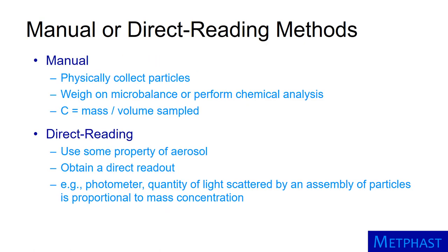The method of aerosol sampling may be manual or direct reading. In manual methods, particles are physically collected, usually onto a filter. These filters are then weighed to determine the mass of collected particles, or analyzed chemically to determine the mass of a certain composition. This weight is then divided by the air volume sampled to obtain mass concentration. In contrast, direct reading methods use some property of an aerosol to obtain a direct readout of concentration — for example, aerosol photometers use the fact that the amount of light scattered by an assembly of particles is related to their mass concentration.